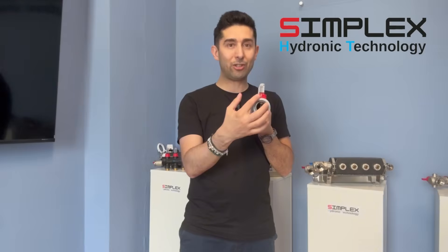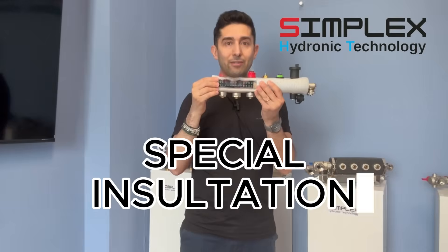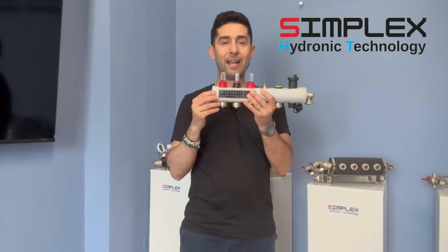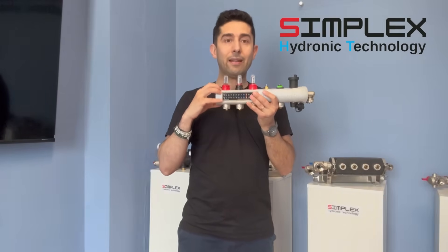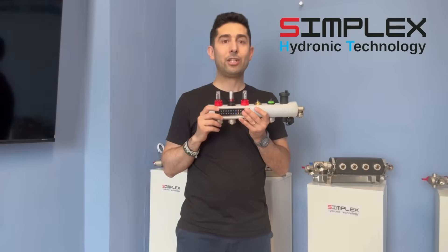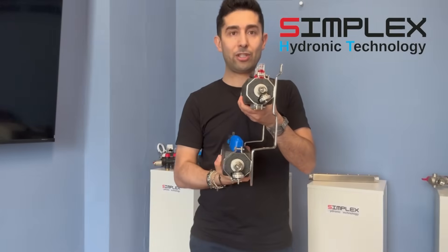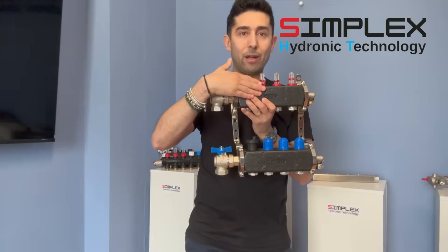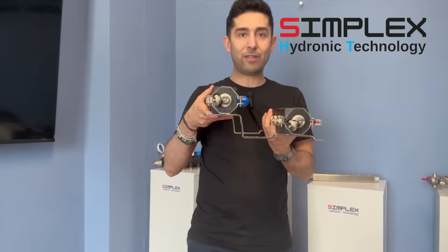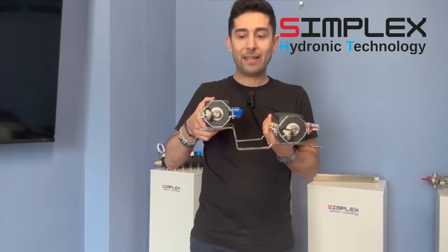It is a manifold in which we have also developed an innovative insulation — an insulation that we apply directly onto the bar ourselves. It takes up very little thickness compared to traditional insulations, which I will show you later. This allows the continued use of brackets that have a maximum height of 8 centimeters, which are absolutely required, especially in Italy, to be installed in the 8 centimeter bar. A much thicker shell is also available, but in that case it is applied directly onto the manifold — a completely different type of insulation, which has the only drawback of increasing the height of the manifold due to the thickness of the polyethylene it was designed with.